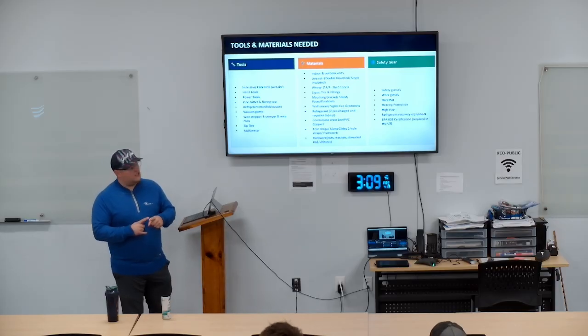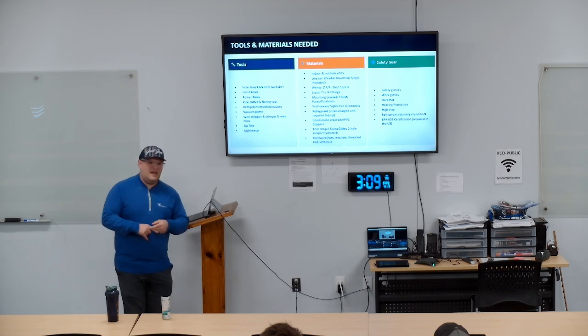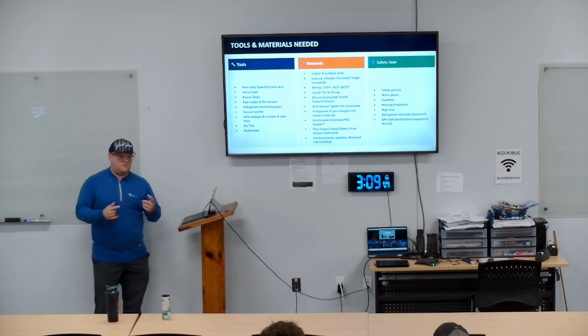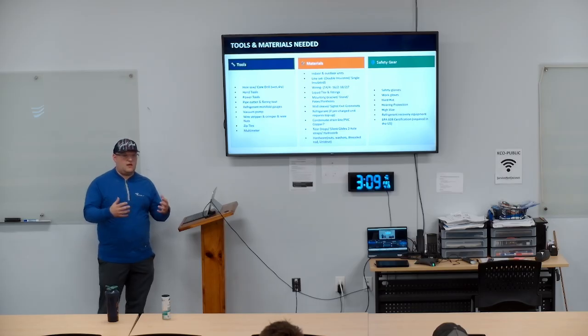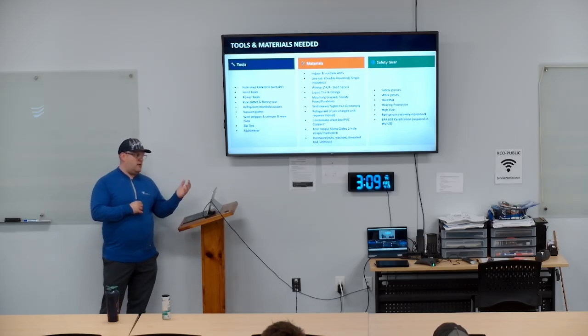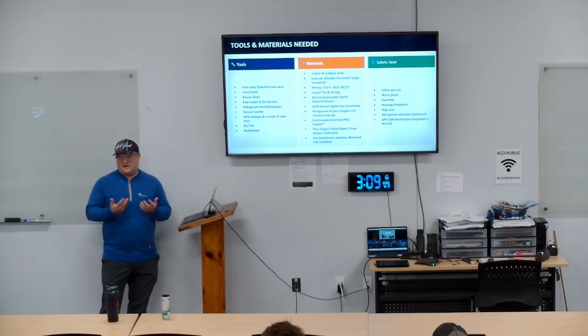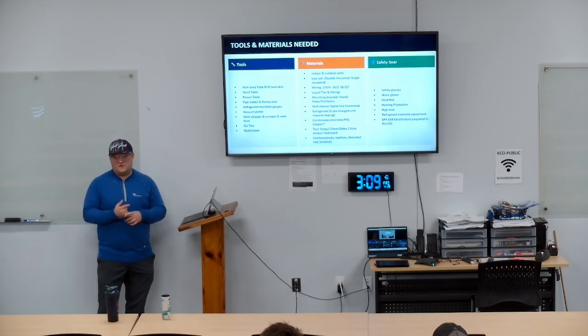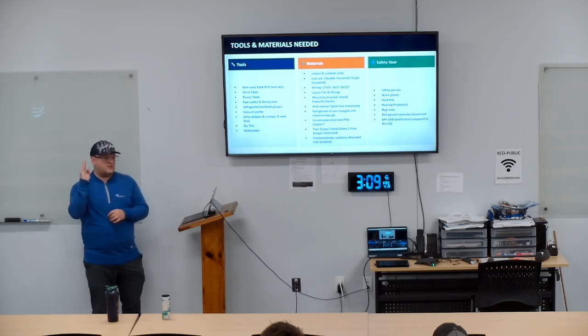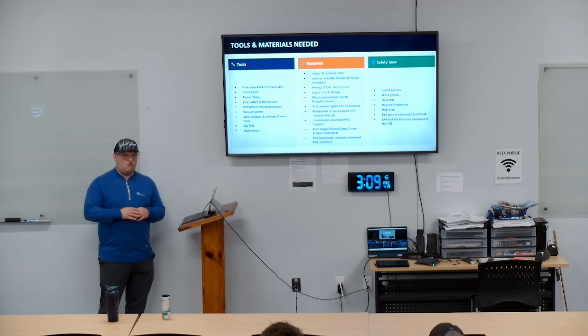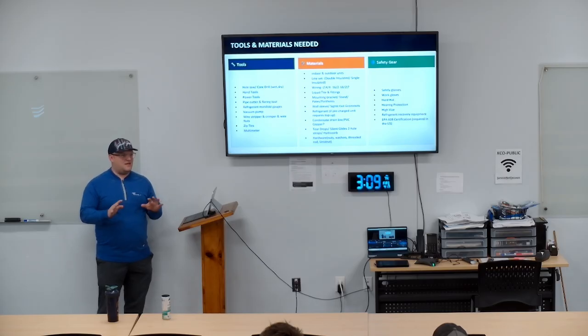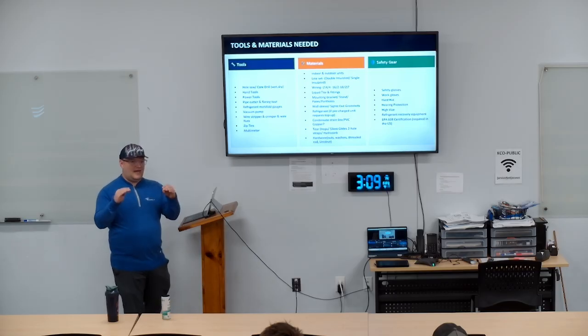The other thing with that is the wiring. Hank and some people have asked me to put together a standard for wiring: if you're running this unit and it's a 3-ton, what kind of wire do you run? And I said, I can't even do that because every manufacturer is different. Samsung uses 16/2 shielded wire on all their splits above about 24,000 BTU.